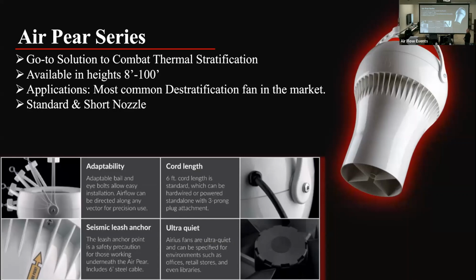Another important point about that is the seismic leash must be installed with the fan. It keeps the fan from moving as well. It's installed at a 45-degree angle, which helps stabilize the fan and keeps it where it's supposed to be. But it's also nice to have up there as a safety feature. With that bail handle, the fan is very solid, very well made. They don't really come out of the ceiling or anything, but it's nice to have that secondary safety feature there as well.